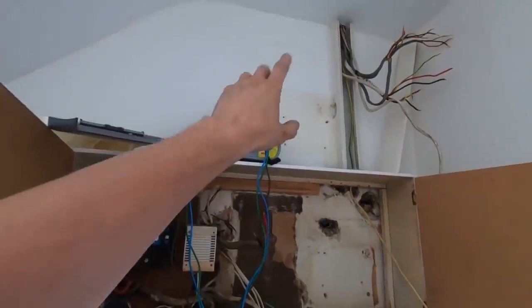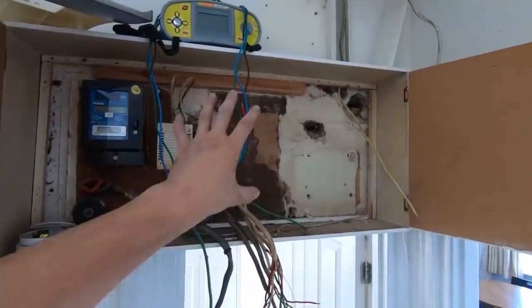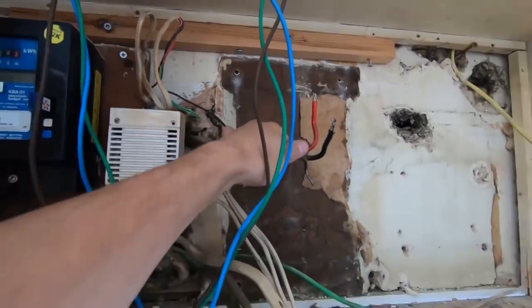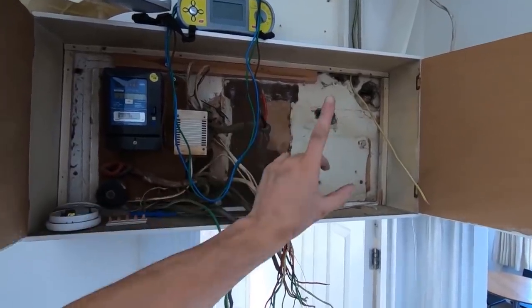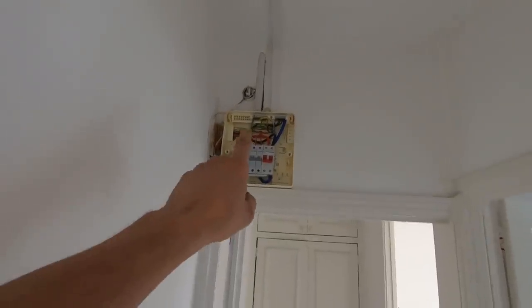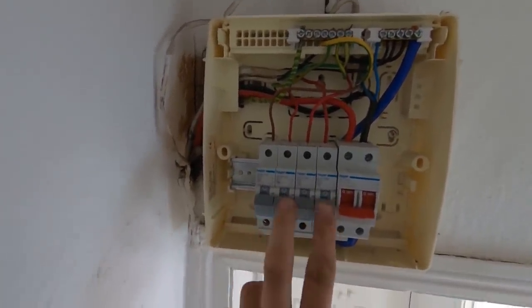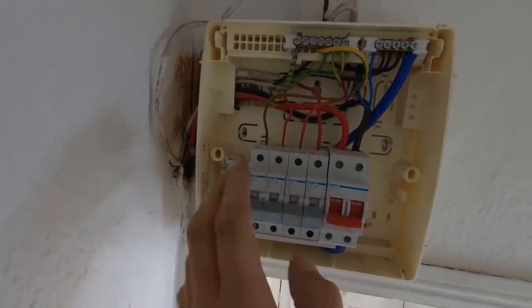That's where I've got up to. I've taken that board out, got rid of that, and those are the cables which were going into that board. I took this one out too - that's now gone. Just taking the tails out of the meter. That was the old sub-main going to the board upstairs. So I've got a nice space there ready to fit a new RCBO board in. What I may well do is change this board up here as well. We've currently got a 2.5 on a 32 and a 1mm on a 32 - but that's not the end of the world. The problem is that sub-main there - that's just been installed like that from new and I can't leave it like that.